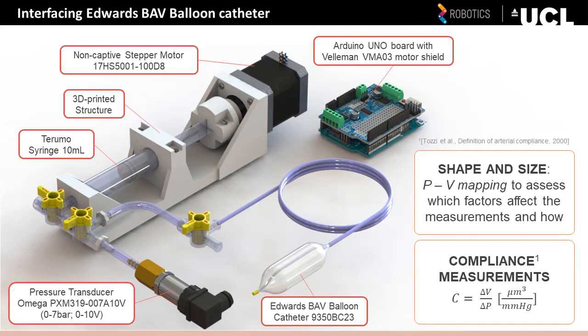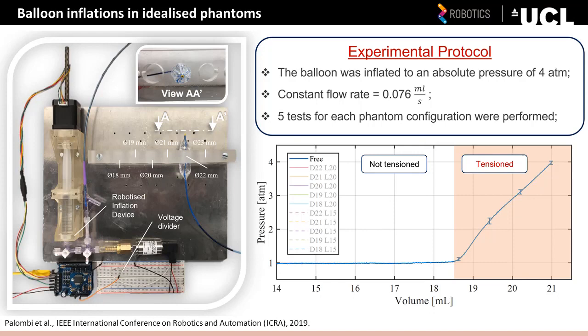We have looked into the development of a valvuloplasty robotic balloon catheter capable of determining the size and mechanical properties of the aortic annulus, which would allow extracting additional relevant information from a device already part of the TAVI procedure. We developed a robotic system capable of controlling balloon inflation and constantly acquiring intra-balloon pressure and volume data. The system is composed of a rapid prototype syringe pump, a controller equipped with a motor shield and an absolute pressure transducer, interfaced with a non-compliant 23 mm balloon catheter. The robotized syringe pump was used to inflate the balloon inside different idealized annular phantoms, obtained by machining acrylic plates with different thicknesses.